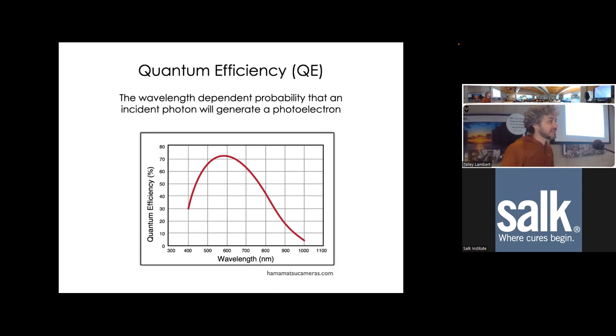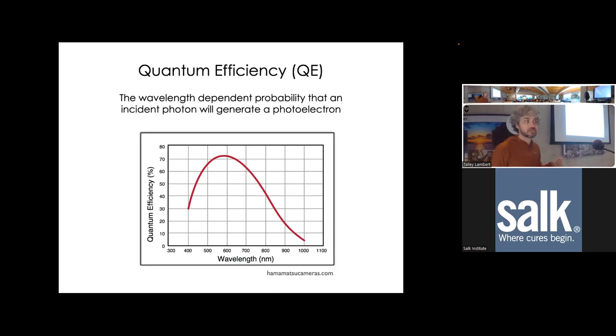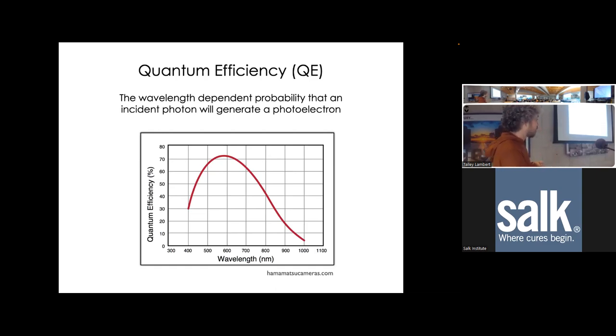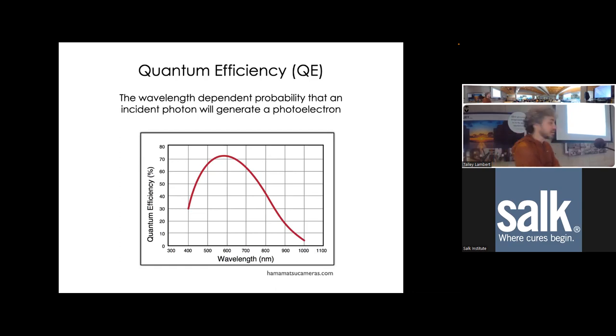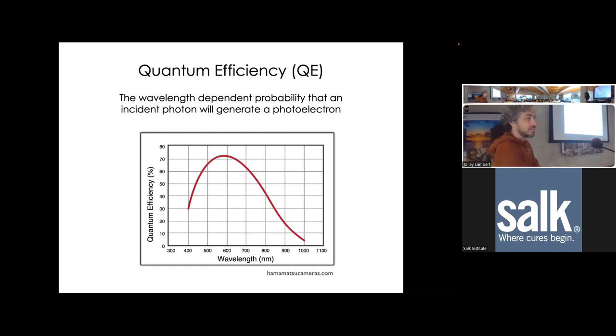There is a metric called quantum efficiency that is super important for any detector. It is the wavelength-dependent probability that an incident photon hitting that photosensitive material will actually generate an electron. Sometimes it will just pass through and not interact, or it'll get absorbed but dissipate as heat and not liberate an electron. This camera from Hamamatsu shows about 70-72% probability if you shine 580 nanometer light. However, if you shine far red light, 90% of the time it's not going to register.